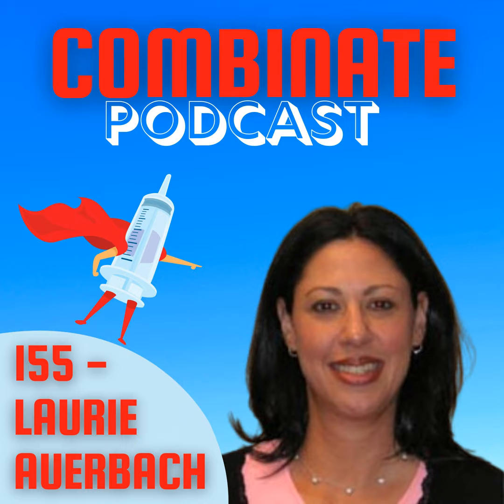the Part 4 call-outs. But for example, and this is something I try to explain when I do mock audits, I use process validation as a good example. Process validation from a device or combination product standpoint is still applicable, even though it's not one of the Part 4 callouts. It's analogous to 211 requirements, but you look at it through the lens of a device or combination product. But when the inspector writes up an observation, they have to reference the 211 requirement because it's not one of the 820 callouts. So it explains that as well.